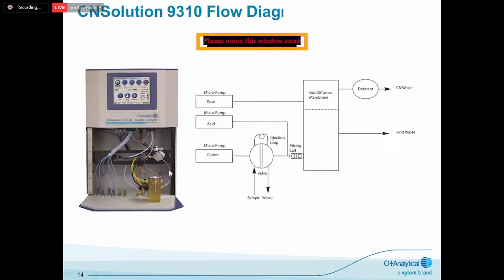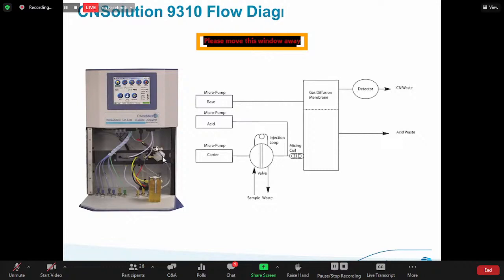And out of this, it flows directly into the amperometric flow cell, which you see here, and which, by the way, we'll mention a little bit later, is the same flow cell with just a slight modification for the higher ranges that we might do on the process instrument that is also used in the laboratory instrumentation. That was just brought over into this, because this really is the heart of the instrument right here, this detector.